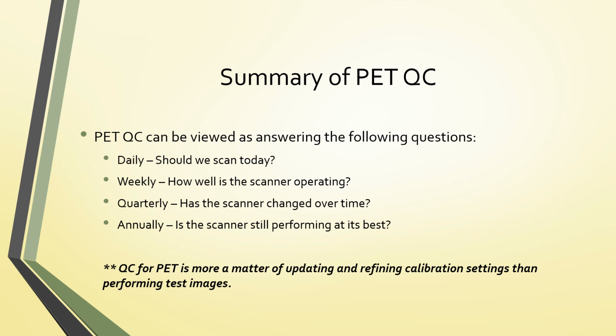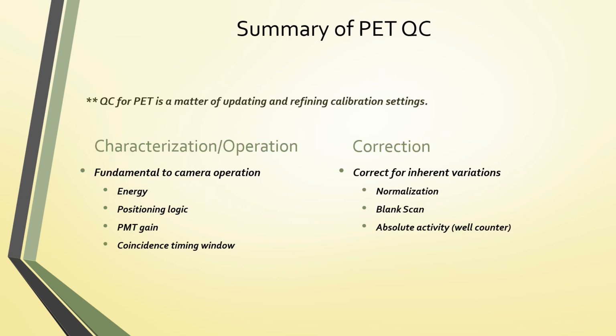QC for PET is more a matter of updating and refining calibration settings than performing test images. This is very different from traditional gamma cameras. We want to recalibrate and tweak the system rather than testing it to see if the test images are going to pass. So QC for PET, like I said, is a matter of updating and refining calibration settings for the most part.